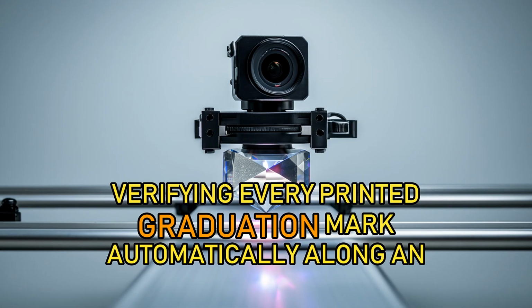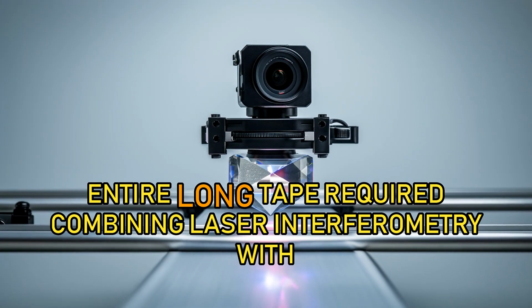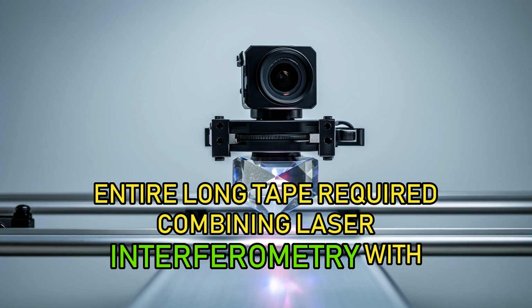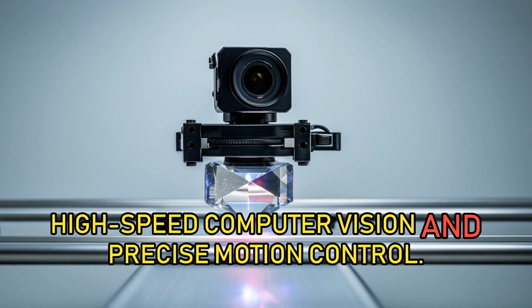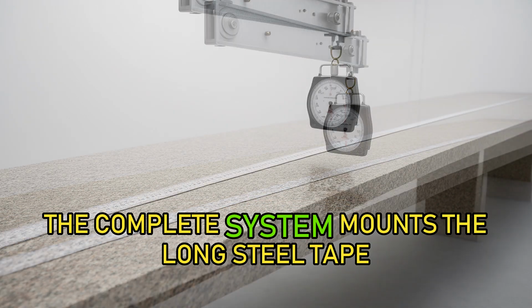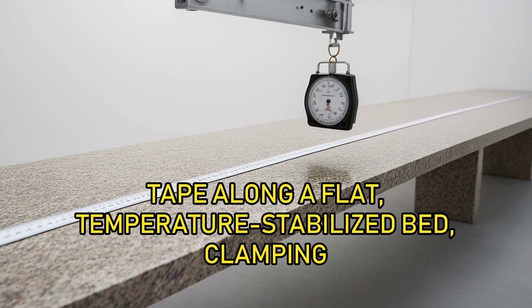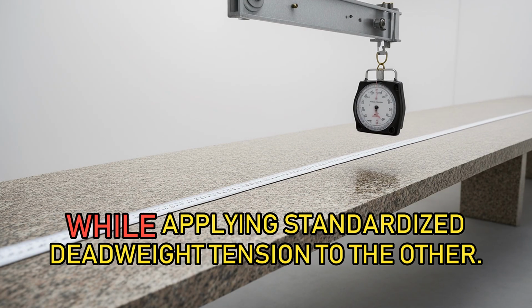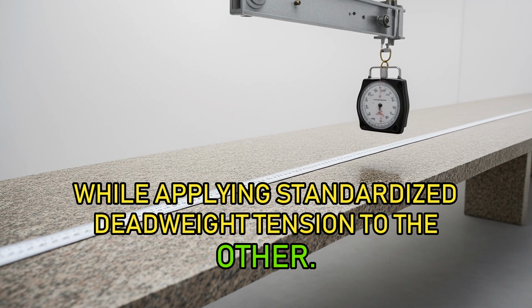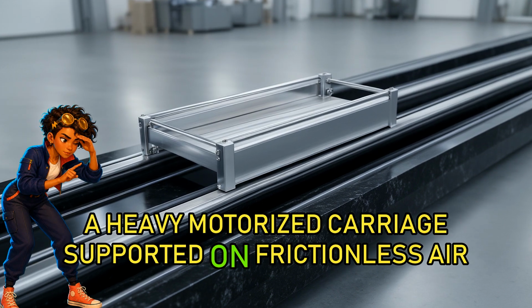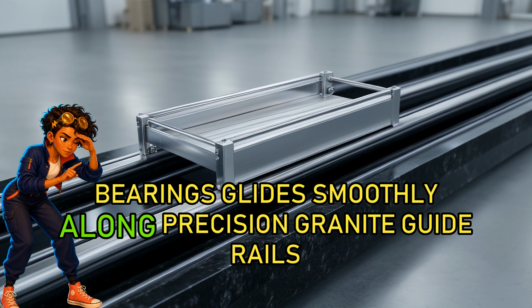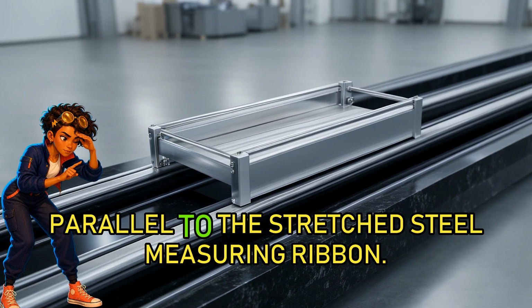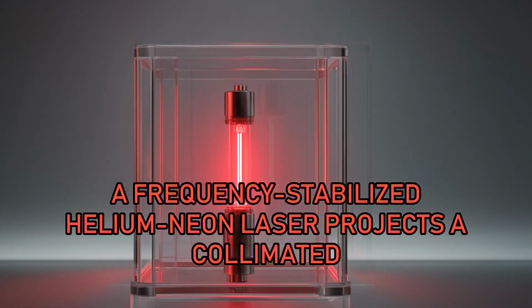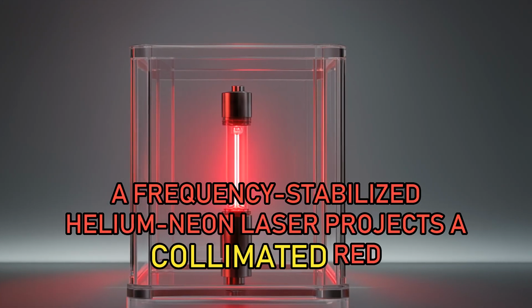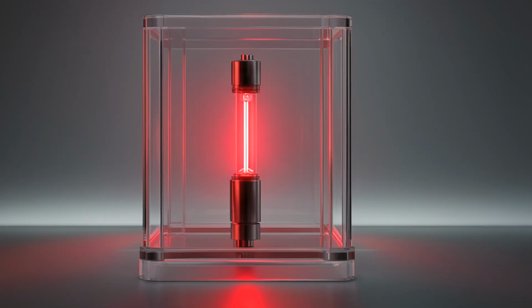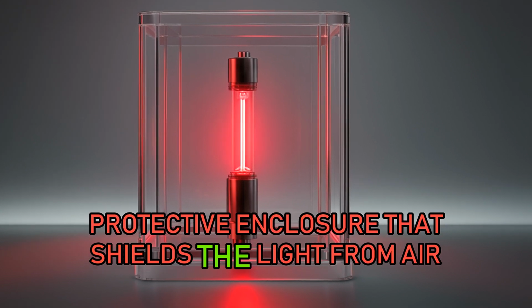Verifying every printed graduation mark automatically along an entire long tape required combining laser interferometry with high-speed computer vision and precise motion control. The complete system mounts the long steel tape along a flat, temperature-stabilized bed, clamping one end while applying standardized deadweight tension to the other. A heavy motorized carriage supported on frictionless air bearings glides smoothly along precision granite guide rails parallel to the stretched steel measuring ribbon. A frequency-stabilized helium-neon laser projects a collimated red beam parallel to the travel path, inside a protective enclosure that shields the light from air currents.